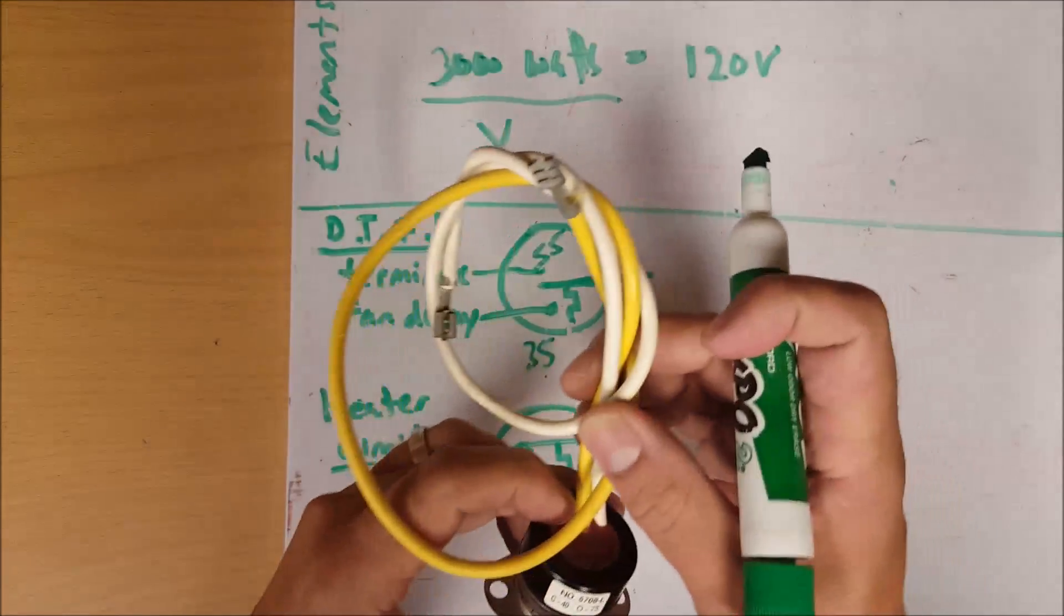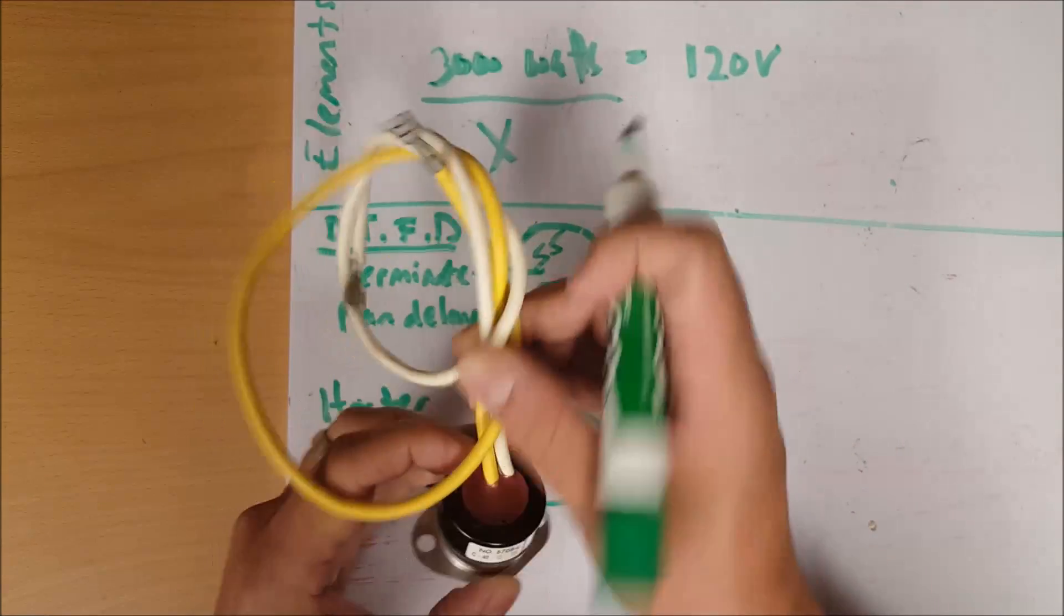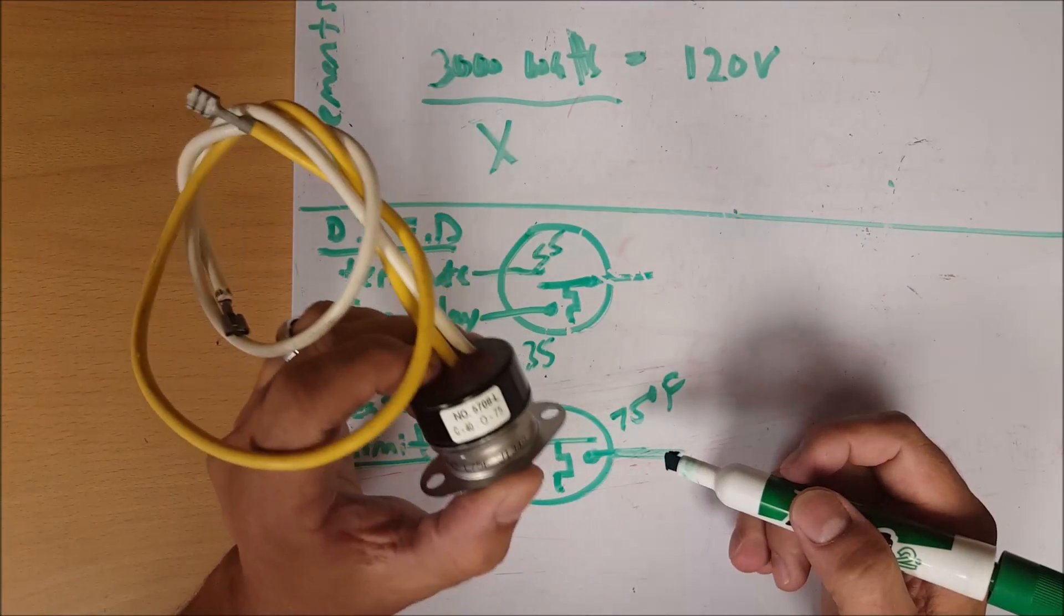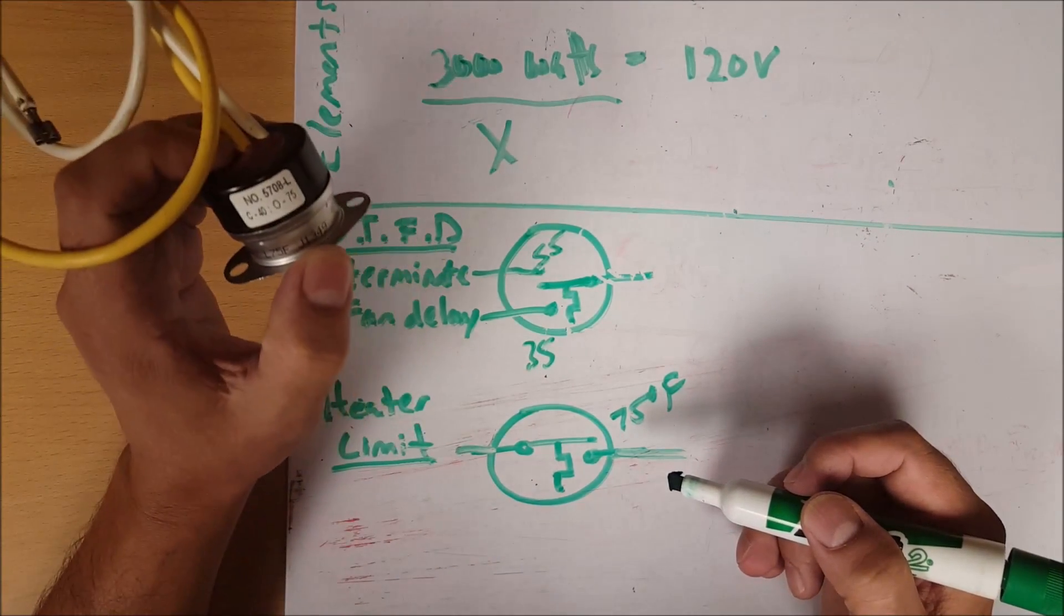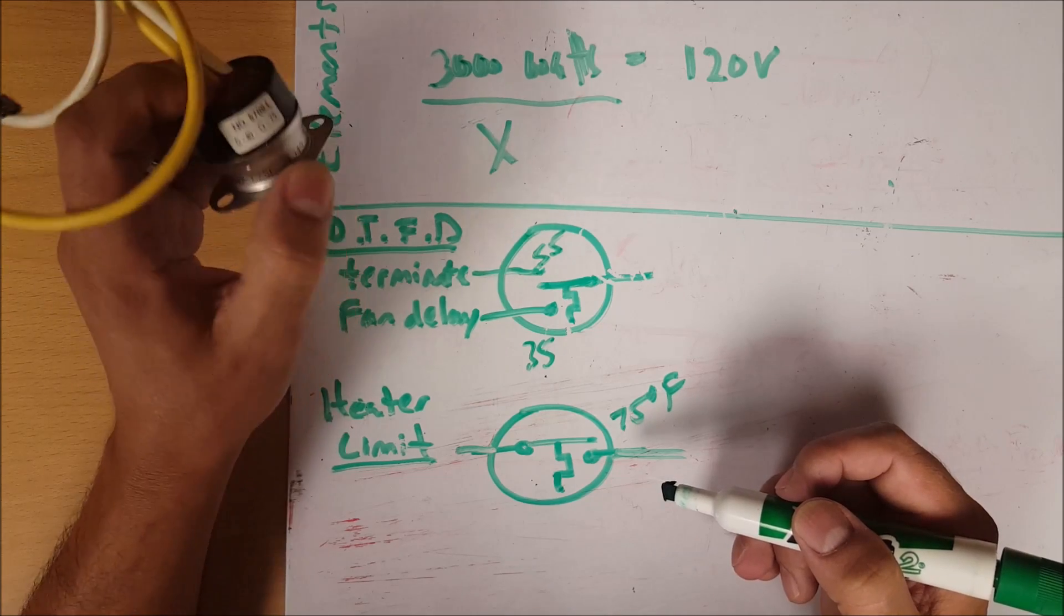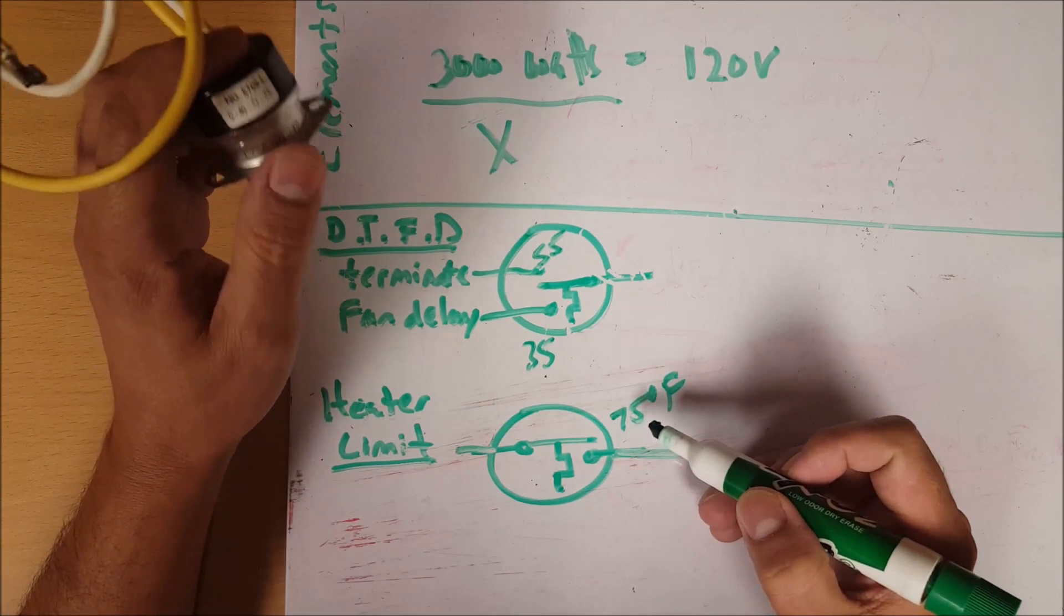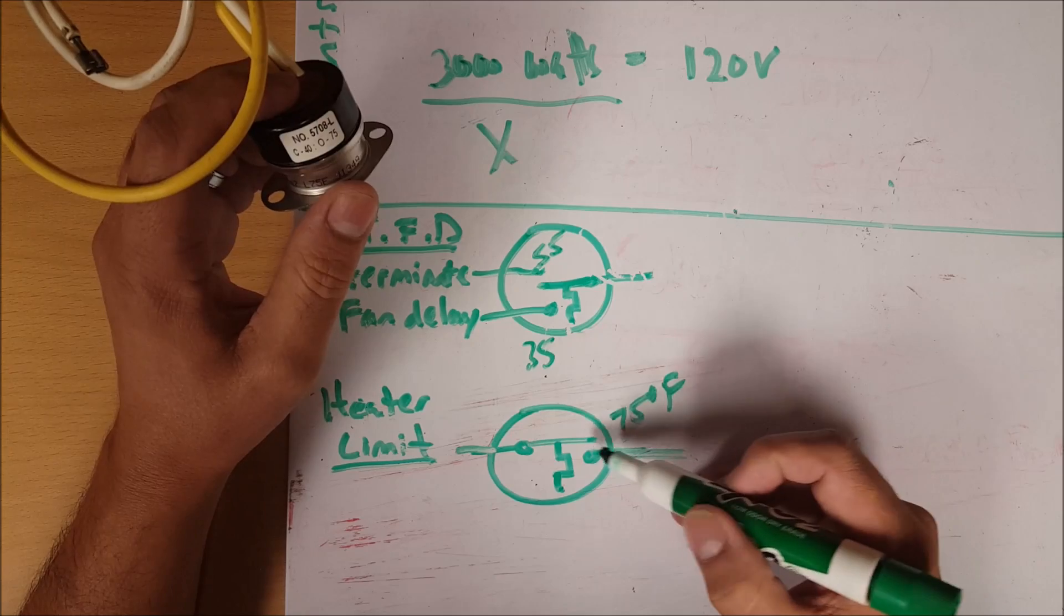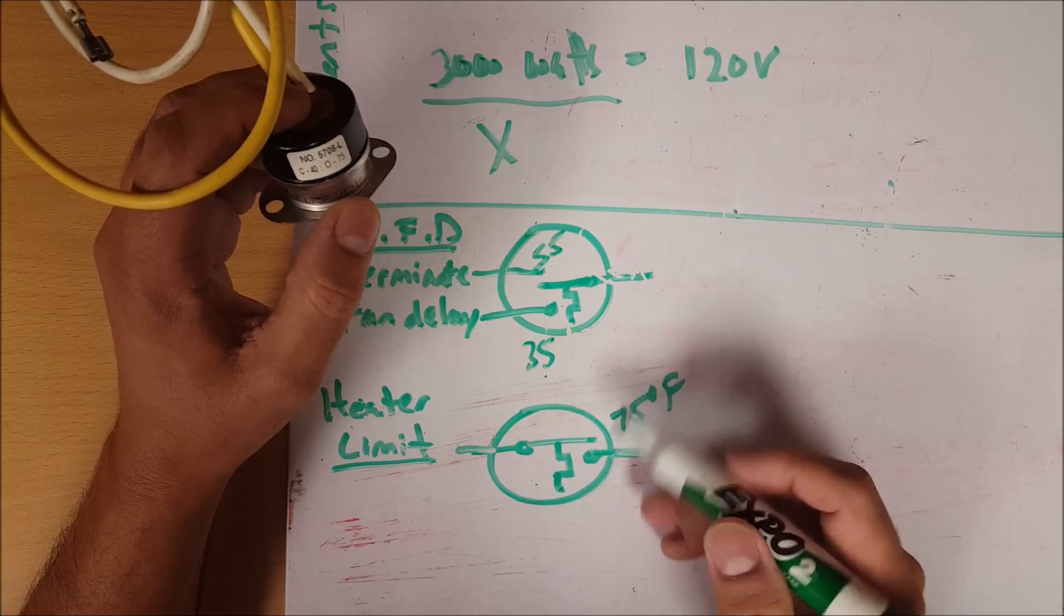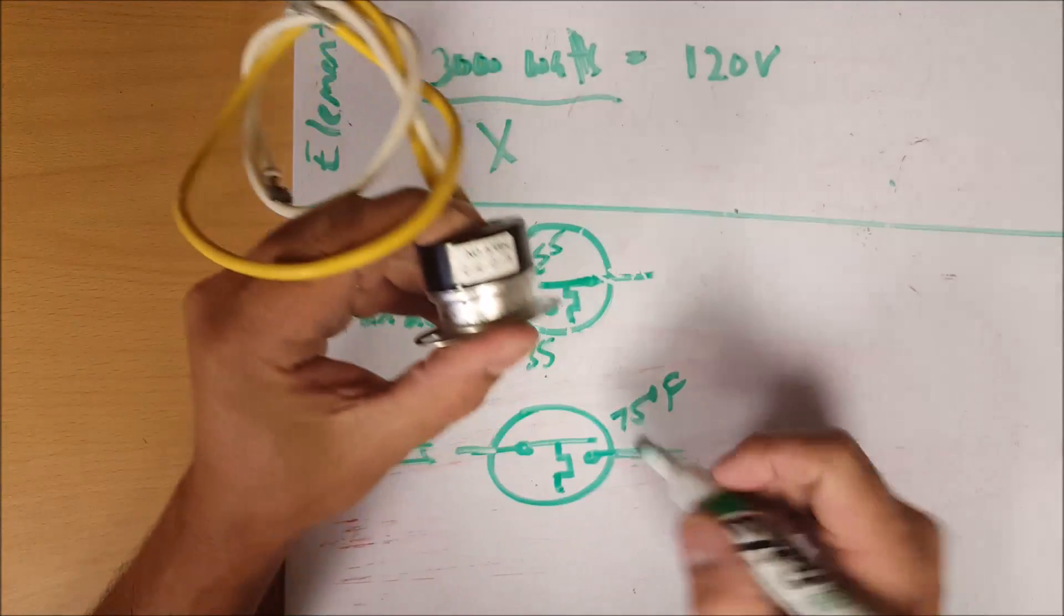These wires are in series with the heater power. So once this breaks open, your heaters are no longer energized, and that's a good thing especially if it's getting above this 75 degree mark. This switch will reset or reclose at 40.